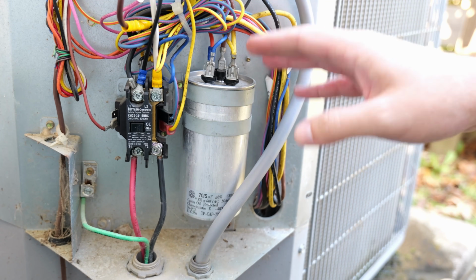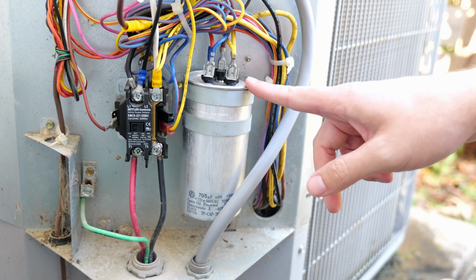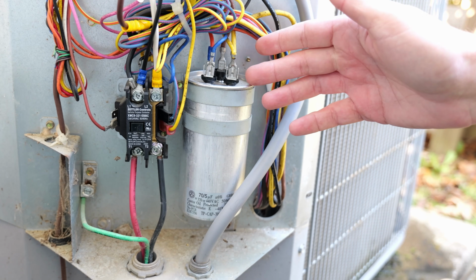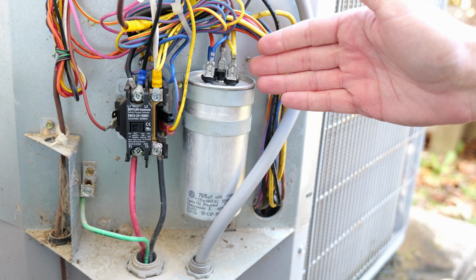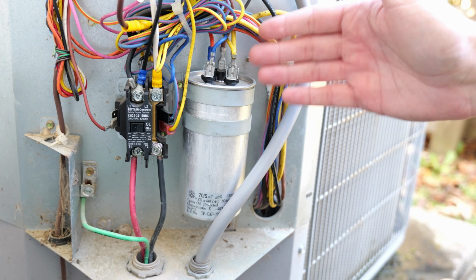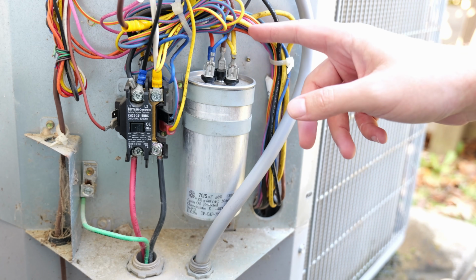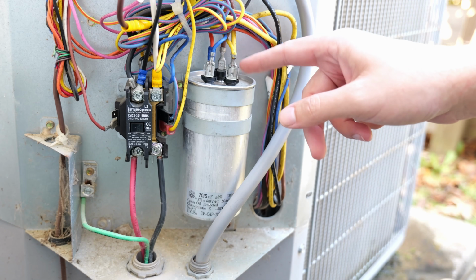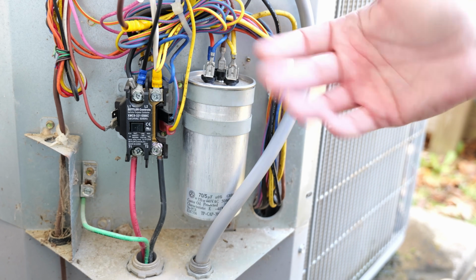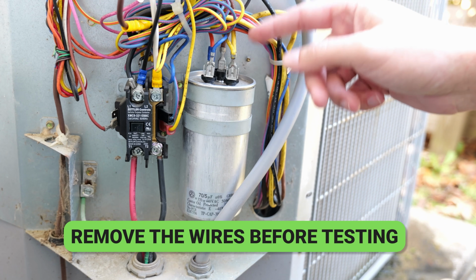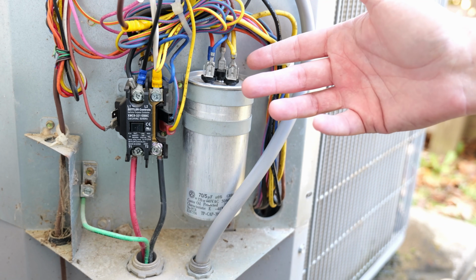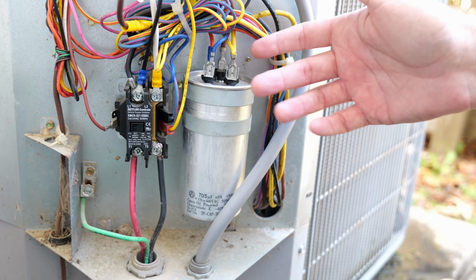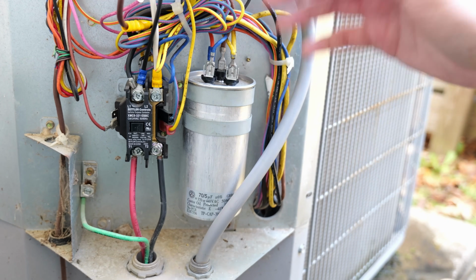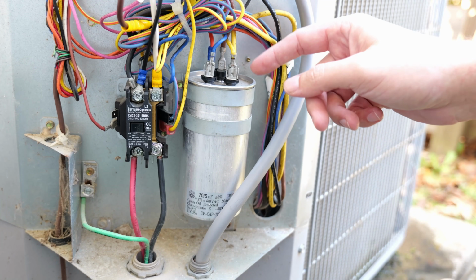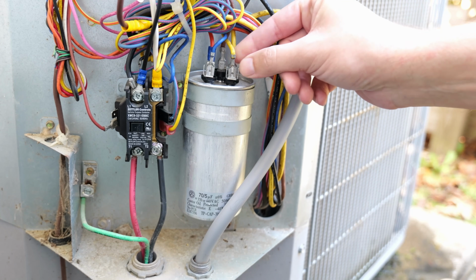One really big mistake that a lot of people make when they do this, and I will also say this is a way that some of the AC companies out there will try to fool people that their capacitor is bad, is trying to take your reading of this capacitor while all of these wires are still connected. The wires on these terminals have got to be removed before doing any testing. You will not get a proper reading. You will not know what your capacitor is actually reading at until that is done. So it's something to look out for if somebody's doing it for you, and of course something that I always want to do before I actually take my reading.